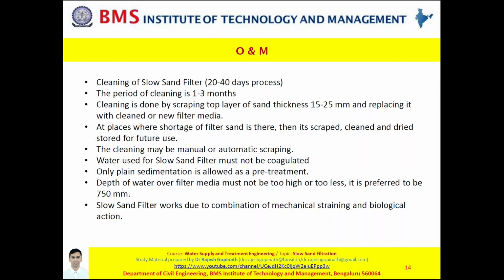Now, to recap, the cleaning may be manual or automatic when it comes to scraping the top layer. Also, as mentioned in slide 15, as I have insisted several times during the operation, the water which enters slow sand filter should come directly from a sedimentation tank and not from a coagulation unit. We should also ensure that the depth of water over the filter media is neither too high nor too less, and it is most preferred to be 750 millimeters.